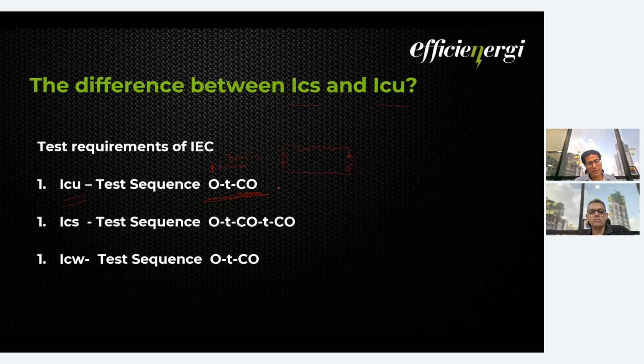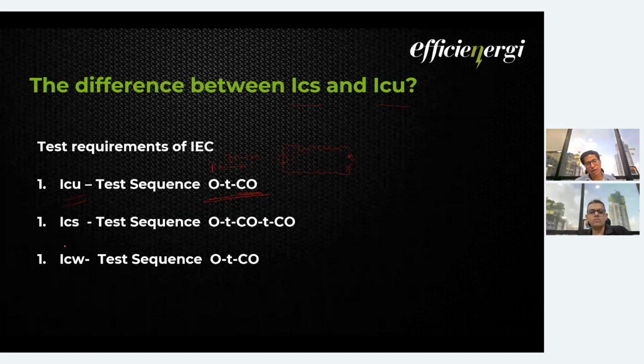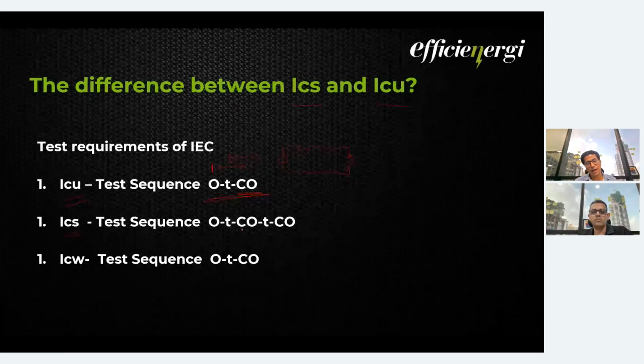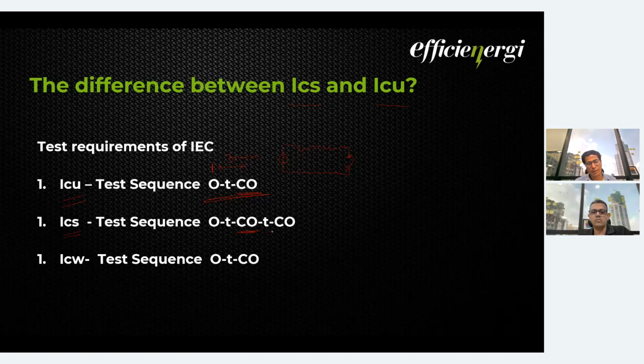Now ICS is the test sequence O-CO, CO, where closing and opening occurs first, then there is some time gap, and again there is a closing and opening on a short circuit. So this is basically a repeated test. The difference is that the ICS value is given for repeated short circuits. The breaker has to withstand repeated short circuits for this particular value, that is ICS, whereas ICU is only a one-time test.